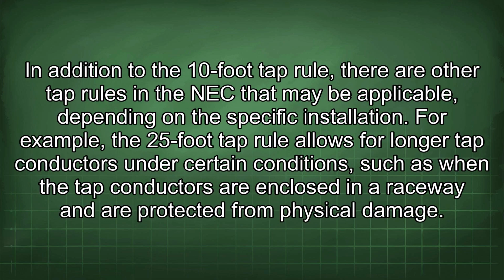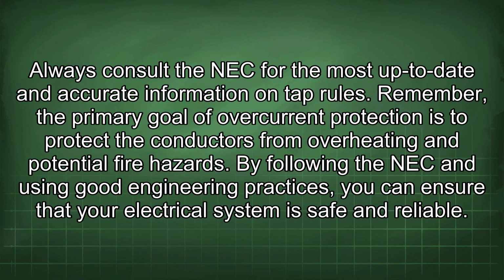In addition to the 10-foot tap rule, there are other tap rules in the NEC that may be applicable depending on the specific installation. For example, the 25-foot tap rule allows for longer tap conductors under certain conditions, such as when the tap conductors are enclosed in a raceway and are protected from physical damage. Always consult the NEC for the most up-to-date and accurate information on tap rules. Remember, the primary goal of overcurrent protection is to protect the conductors from overheating and potential fire hazards. By following the NEC and using good engineering practices, you can ensure that your electrical system is safe and reliable.